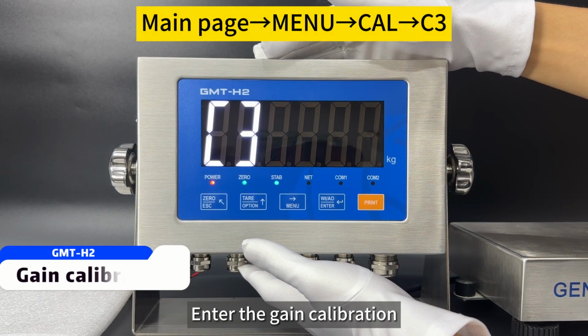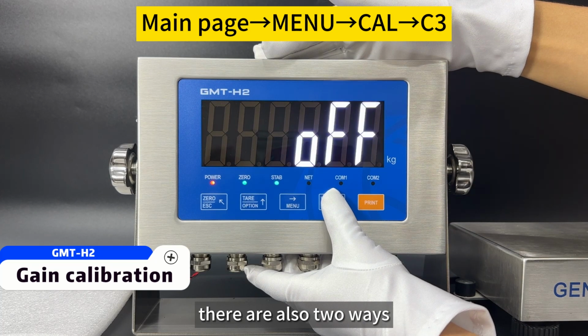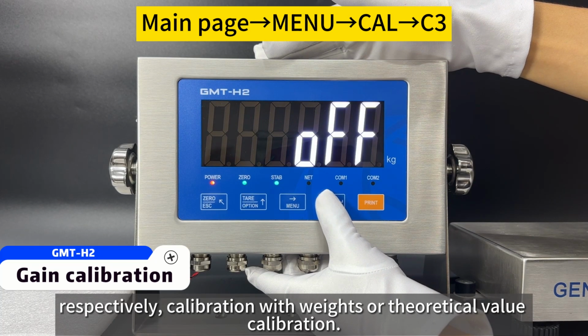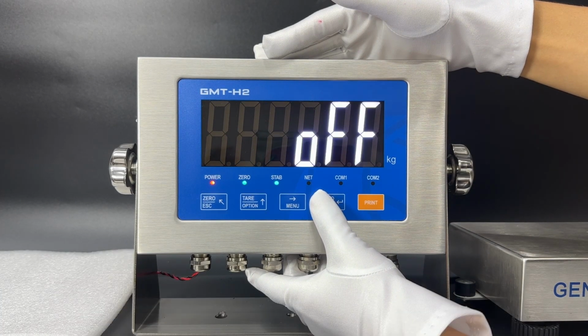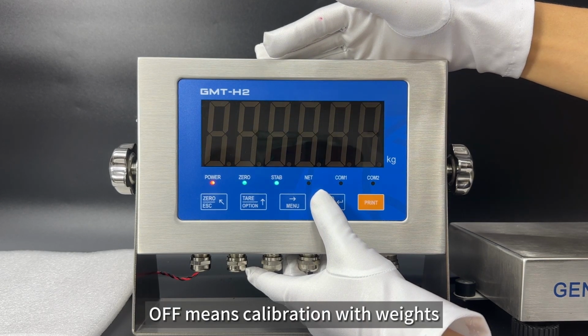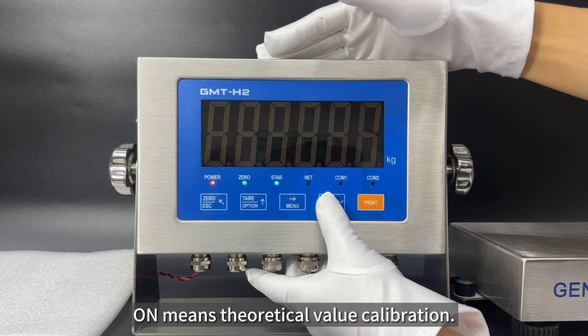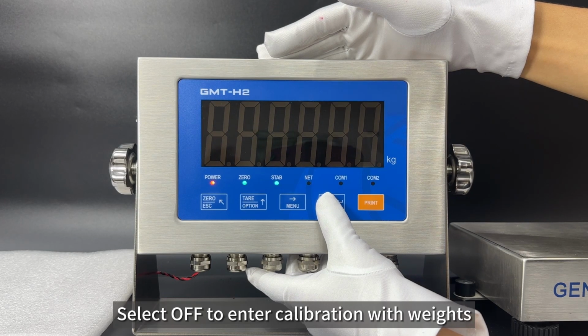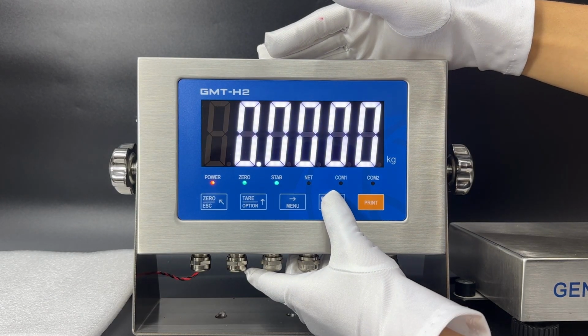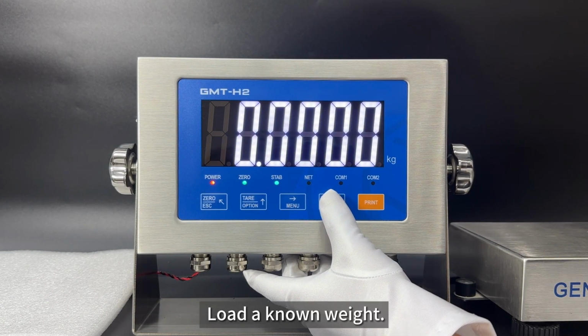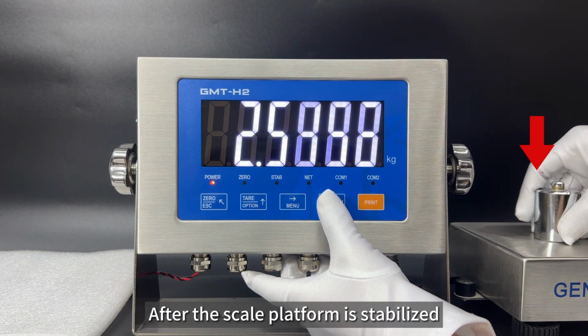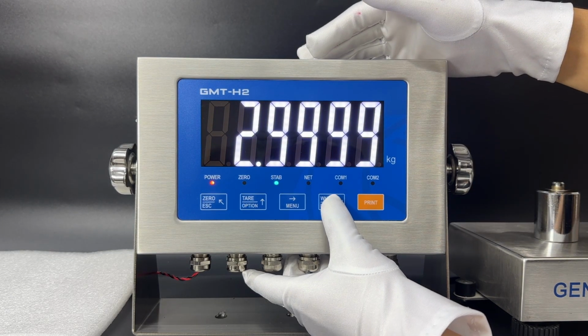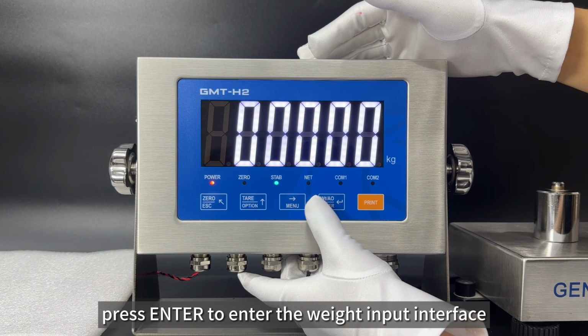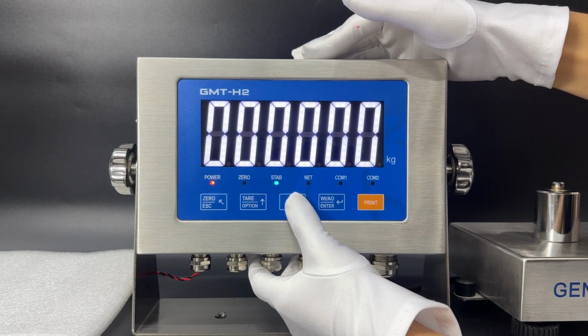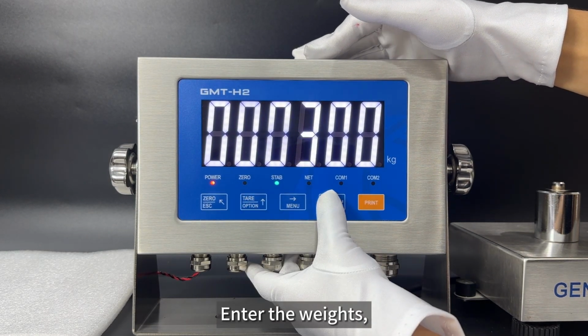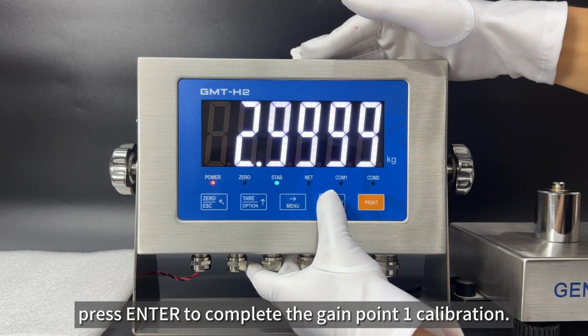Enter the gain calibration. There are also two ways, respectively, calibration with weights or theoretical value calibration. Off means calibration with weights. On means theoretical value calibration. Select off to enter calibration with weights. Load a known weight. After the scale platform is stabilized, press enter to enter the weight input interface. Enter the weights, press enter to complete the gain point 1 calibration.